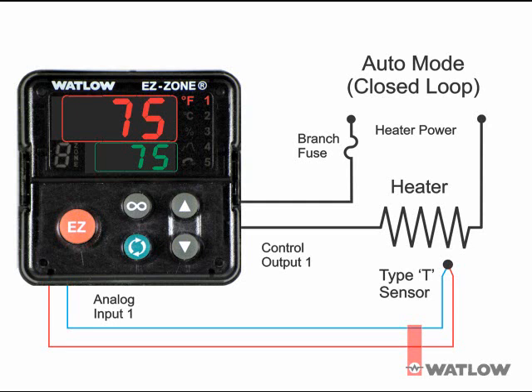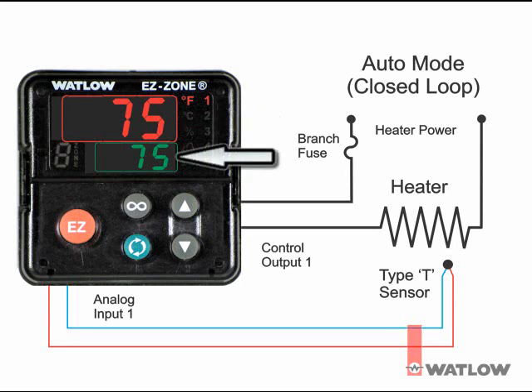Closed loop control uses the process sensor to determine the difference between the process value, shown here in red on the upper display, and the closed loop setpoint, shown here in green on the lower display. The controller applies or removes power to a control output to reduce the difference.